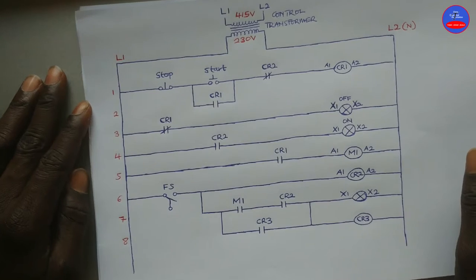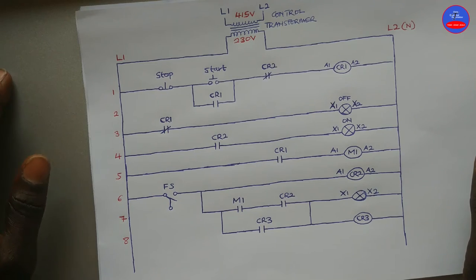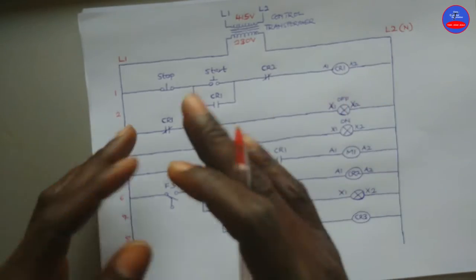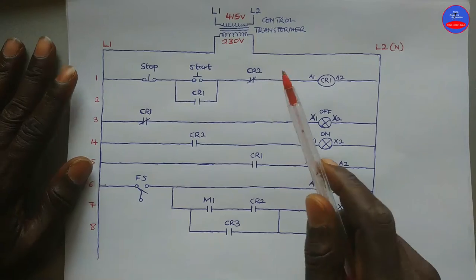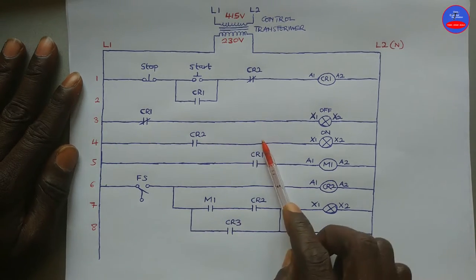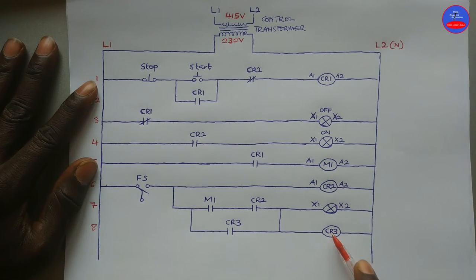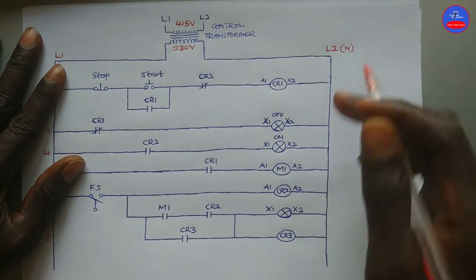Now let's move on to the next one, which is numerical cross-referencing. Numerical cross-referencing helps us to identify the location of components and contacts in the control diagram. In this diagram, we are going to identify the number of contacts on each coil device. Our coil devices are CR1, M1, CR2, and CR3. We put the numbers in parentheses at the right side of each of these coil devices.